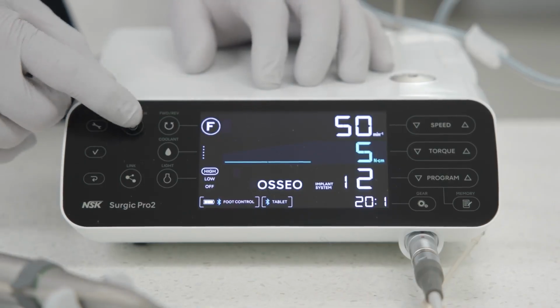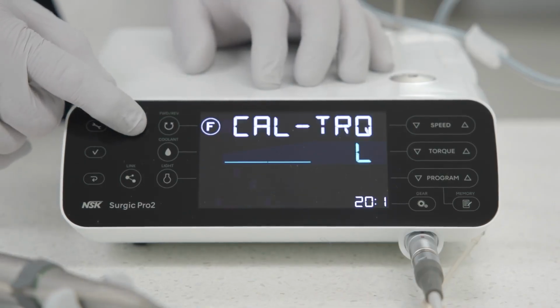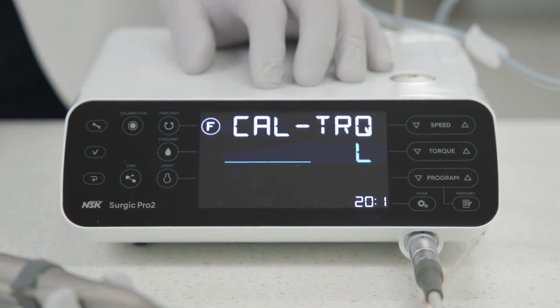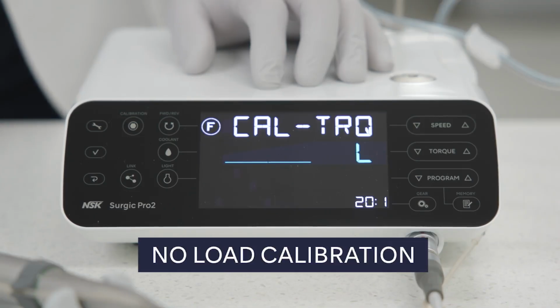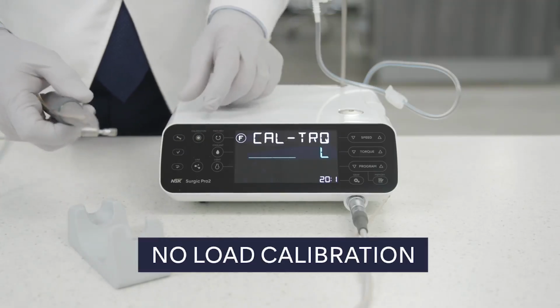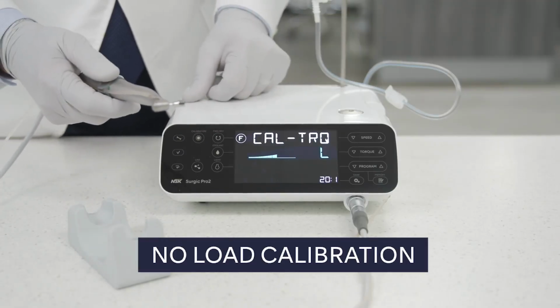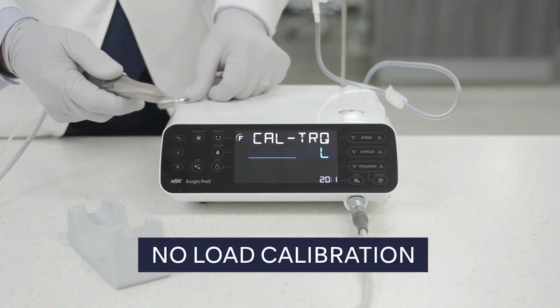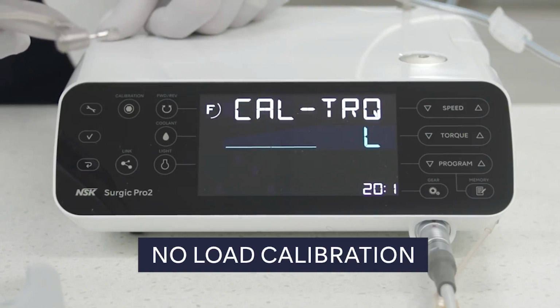Mount the 20:1 handpiece on the motor and insert the calibration burr. Press calibration until you hear a beep. The display will switch to calibration mode and Cal TRQ is displayed. Now you're ready to calibrate. For no-load calibration, an L is shown on the display. Hold the motor in one hand and press calibration. A beep sounds and the burr begins to rotate for a few seconds. Once calibration is complete, you will hear another beep and pass appears on the display.